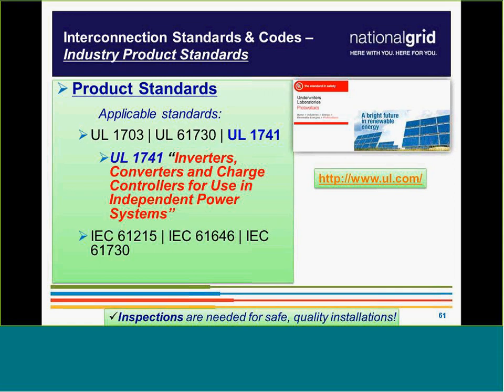After C37.90 and other industry standards, we also have product standards. Any distributed generator that is UL 1741 listed will have a bit of a simpler process when connecting, because it's gone through certain islanding tests and other checks. So if you see something that's UL 1741, or very soon UL 1741 SA - if you're familiar with Rule 21 in California, UL 1741 SA is starting to show up on inverters - that's something you definitely want to look for.